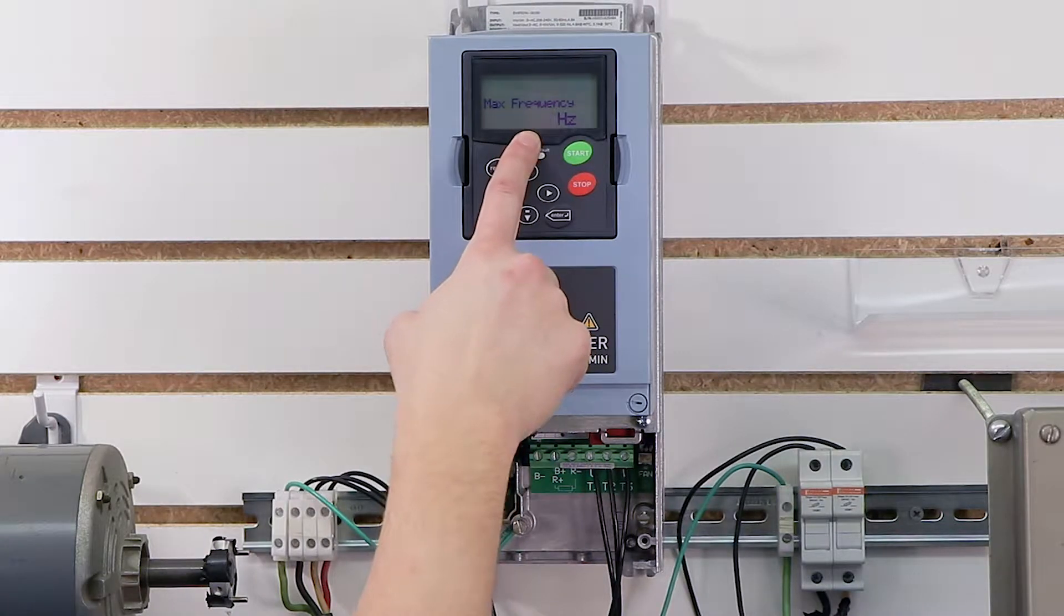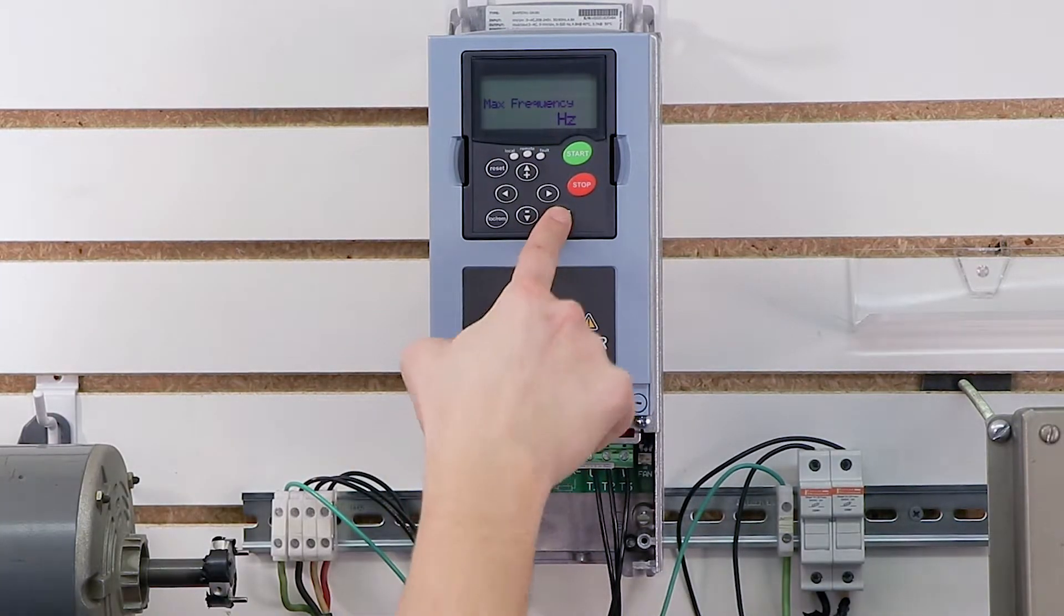For maximum frequency, I'm going to go ahead and set mine to 60 Hertz because that's actually the rated frequency on my motor's nameplate. So I'm going to press enter for that one.